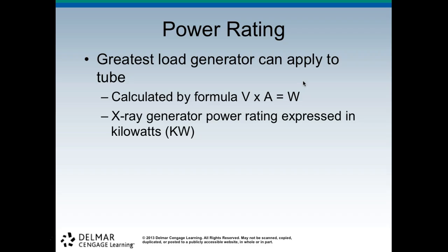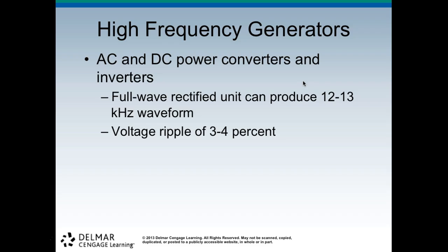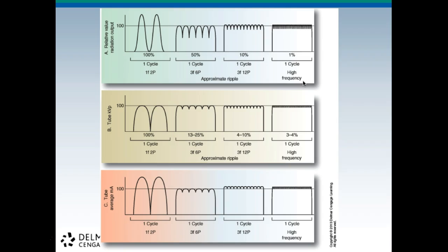Your power rating is the greatest load the generator can apply to the tube. So you calculate the formula by voltage times amperage equals watts. The X-ray generator power rating is expressed in kilowatts. So high frequency generators, you take AC to DC power, converts and inverts. So full wave rectified units can produce 12 to 13 kilohertz waveforms. So voltage ripple is 3 to 4%, which is really good.